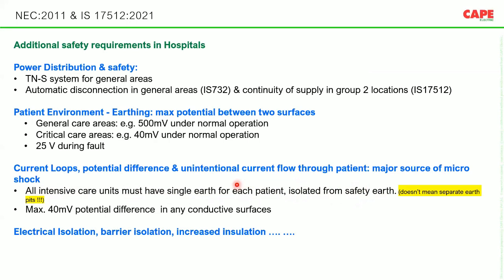It doesn't mean that you need to have a separate earth pit. The recommendation here is each single patient or an area where you have an ICU, each patient area should have only one earth. That means a very good equipotential bonding must be made, and this can be isolated from safety earth. This is a kind of functional earth. We will discuss it maybe in another program, because this itself is a much bigger subject. Maximum 40 millivolt potential difference in any conductive surfaces must be made.